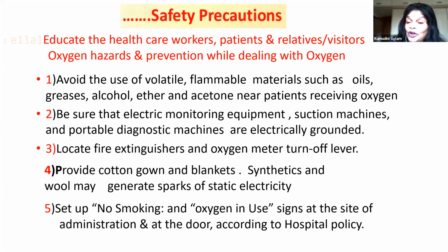Be sure that electrical monitoring equipment, suction machines and portable diagnostic machines are electrically grounded. Then locate the fire extinguisher and the oxygen meter turn-off lever, because training is a must nowadays: if there is a fire, how to use the extinguisher. Provide cotton gowns and blankets in hospital use; synthetics and wool may generate sparks of static electricity. Set up the no smoking and oxygen in use signs at the site of administration and at the door, according to the hospital policy.